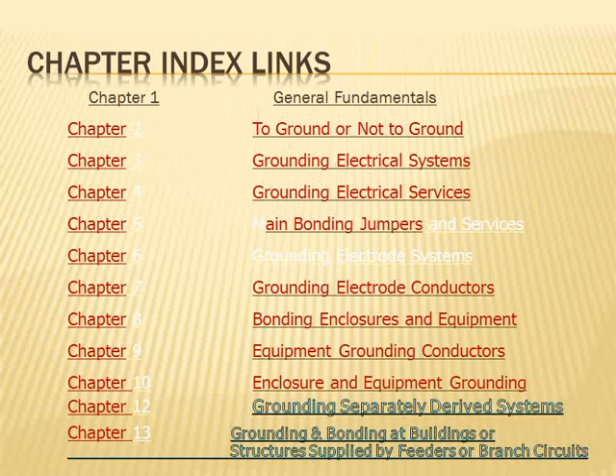So we have a separately derived system. If you own and operate a generator, or you own and operate a transformer, or you own and operate a UPS system, or you own and operate a solar system, you are dealing with something called a separately derived system. I always explain it as you derive a new neutral for the new system. You ground that new neutral, like 208/120, and that's what, in plain English, defines a separately derived system. You own and operate a new transformer. On the secondary side, you create a 208/120 neutral, and you ground it. We'll talk about this one in a second.